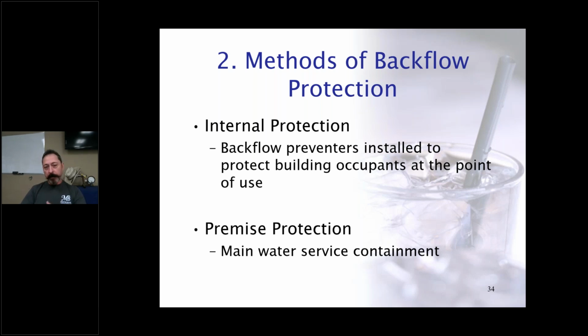Methods of backflow protection. So how do we control these cross connections? Where do we put everything so that we can isolate these cross connections and ensure those contaminants can't enter the drinking water supply? We can do that by adding backflow preventers internally inside a building to ensure that all the cross connections in the building, like the janitor sinks, the fire sprinkler system, the irrigation supplies, the boiler makeup or the water supply to the heating systems, are protected by a backflow preventer. And that protects the occupants of a building. That's really what the plumbing code primarily focuses on, to protect the occupants.